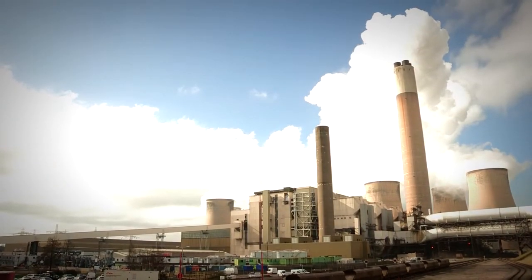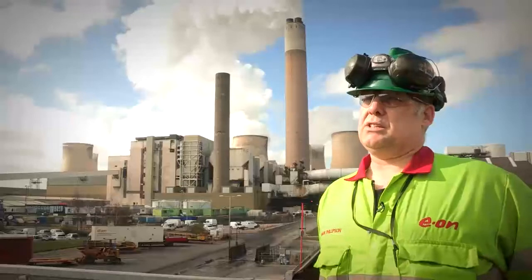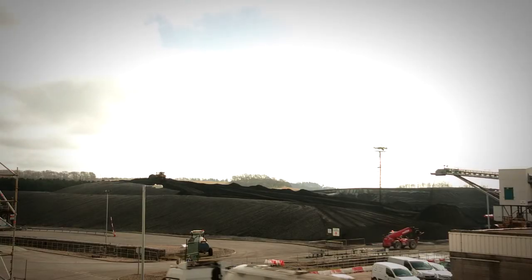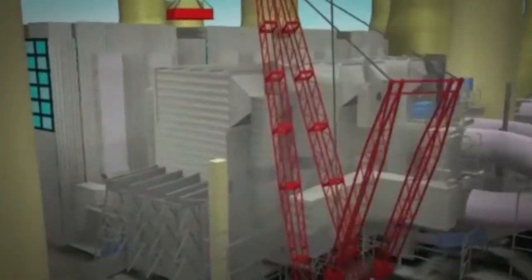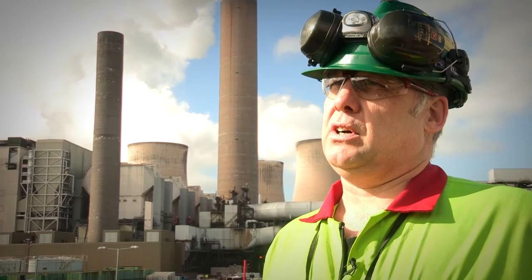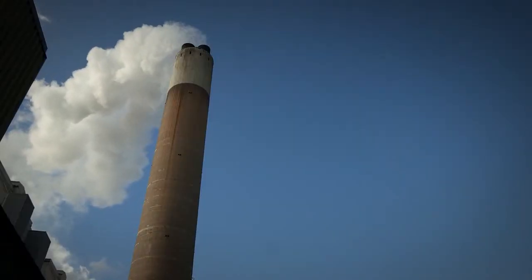When we burn the coal you get obviously different gases. With the SCR we're concerned with the nitric oxide — that's the gas that the government and the EU have deemed that we need to cut down on. Basically what we're doing, we take the gas out of the boiler, we inject ammonia into the gas path, which then neutralizes the nitric oxide and gives a cleaner exhaust gas going out of the chimney.